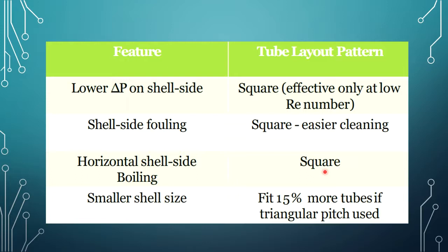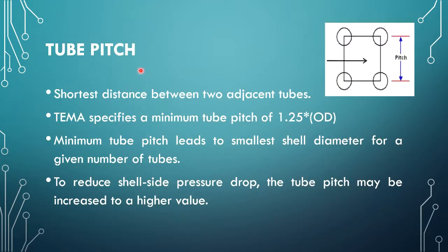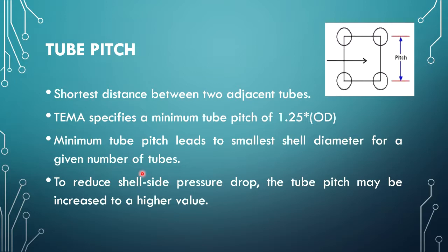Tube pitch is the shortest distance between two adjacent tubes. According to TEMA specifications, the minimum tube pitch is 1.25 times the outside diameter of the tubes. A minimum tube pitch leads to a smaller shell diameter for a given number of tubes. If we need to reduce the shell side pressure drop, tube pitch may be increased. Generally, the range of tube pitch is 1.25 to 1.5 times the outside diameter, and it may be adjusted according to shell side pressure drop requirements.